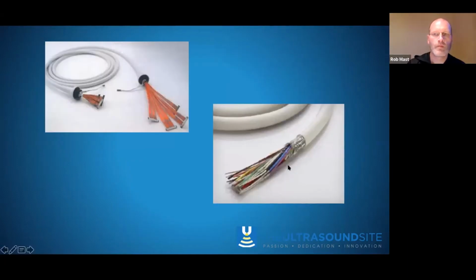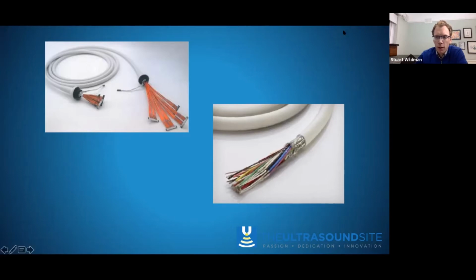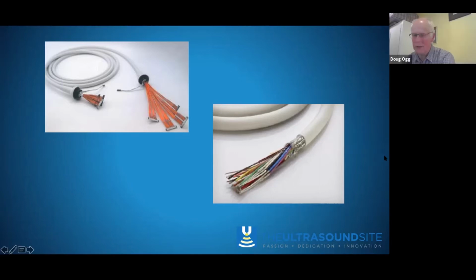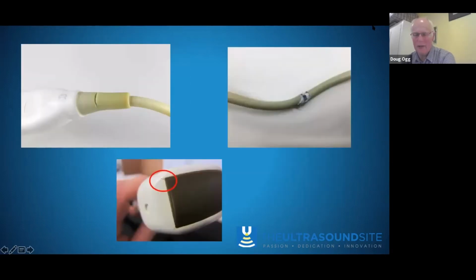And this is what an ultrasound probe theoretically looks like inside. And Doug, maybe I can draw on you to comment about this at this point. Yeah, this is one of the things: the cable outside is smooth, it's white, looks rather boring, but inside there's an awful lot. You've got to remember that the echo information received by the transducer is translated into very, very small voltages, and voltage changes that are happening in the megahertz range. And electricity at very high frequency has some interesting characteristics. It leaks.